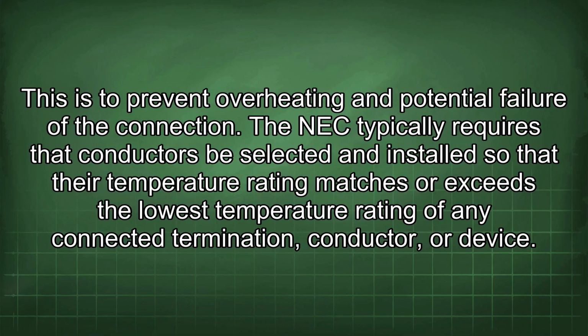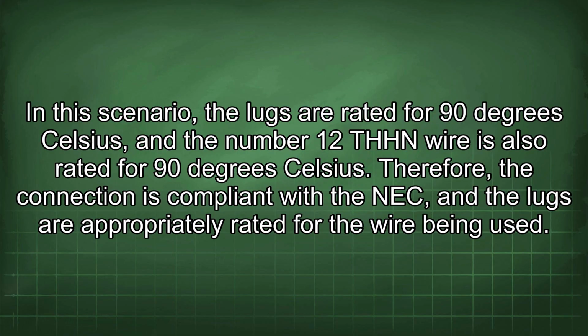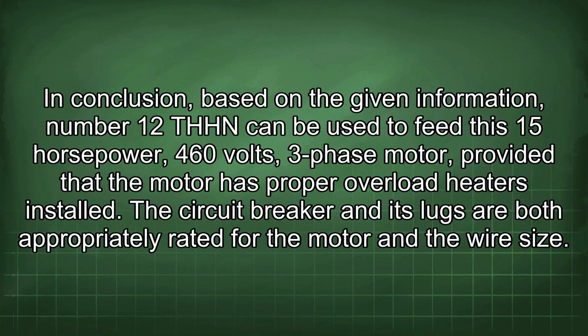The NEC typically requires that conductors be selected and installed so that their temperature rating matches or exceeds the lowest temperature rating of any connected termination, conductor, or device. In this scenario, the lugs are rated for 90 degrees Celsius, and the number 12 THHN wire is also rated for 90 degrees Celsius. Therefore, the connection is compliant with the NEC, and the lugs are appropriately rated for the wire being used. In conclusion, based on the given information, number 12 THHN can be used to feed this 15 horsepower, 460 volts, three-phase motor, provided that the motor has proper overload heaters installed. The circuit breaker and its lugs are both appropriately rated for the motor and the wire size.